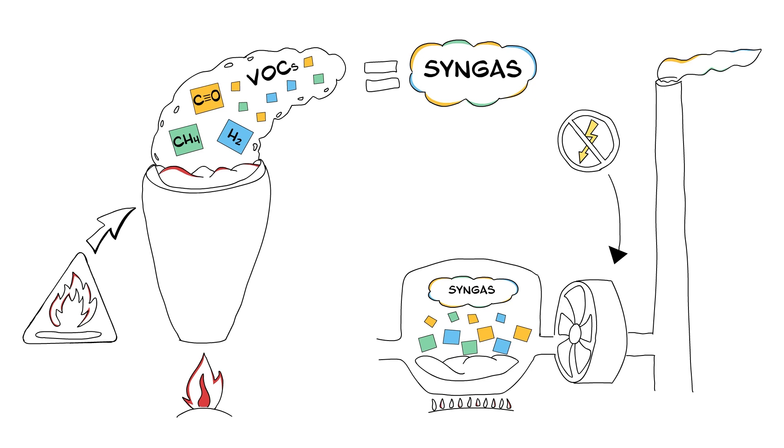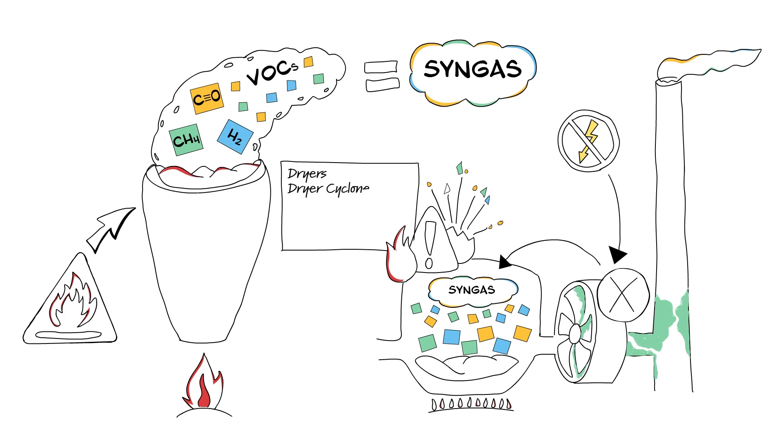Without electrical power to operate extraction fans, syngas can quickly accumulate within the system. Also, a faulty, dirty, or clogged ventilation system may prevent syngas from discharging. Accumulation of sufficient amounts of syngas poses a risk of fire or explosion in the presence of an ignition source and sufficient oxygen. This may occur in enclosed spaces such as dryers, dryer cyclones, combustion chambers, ducts, or pipes.